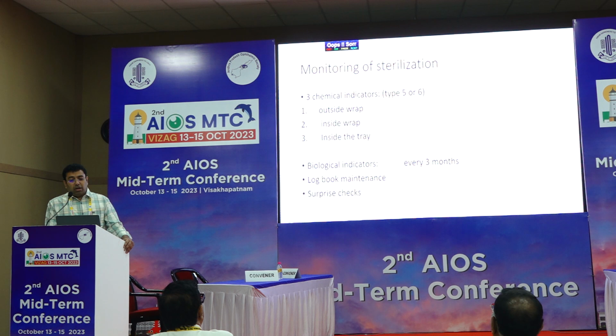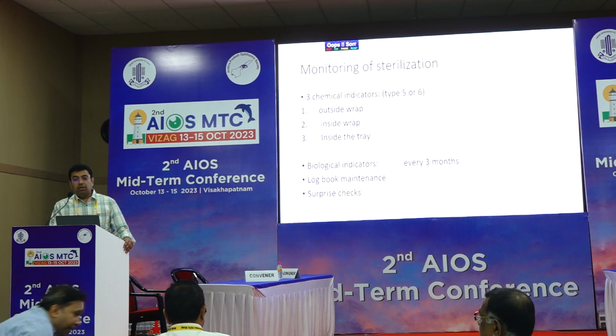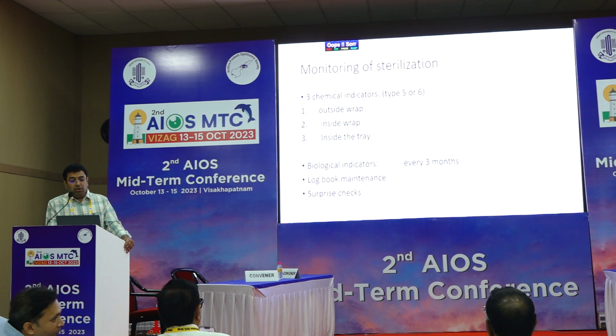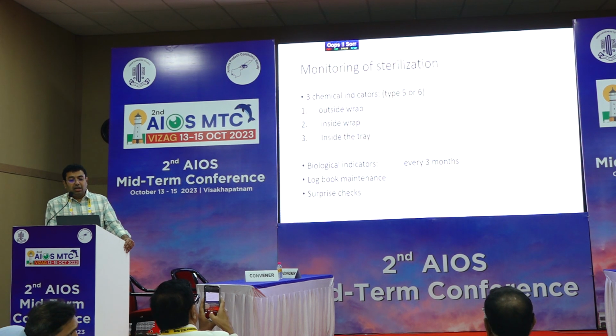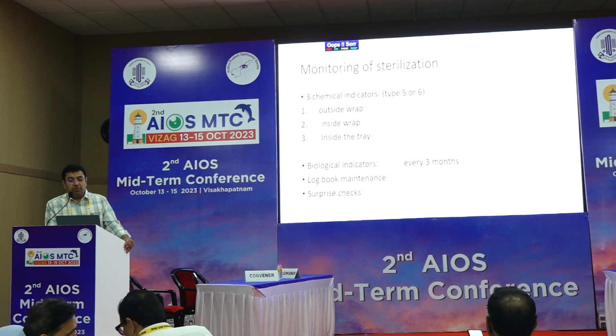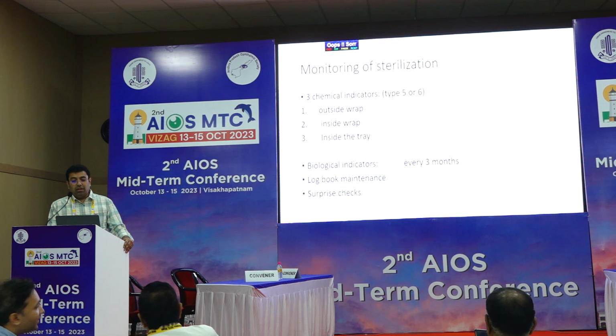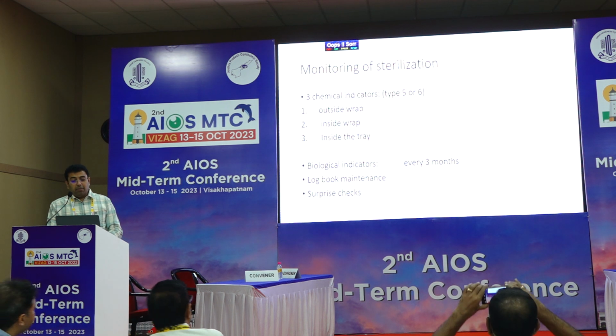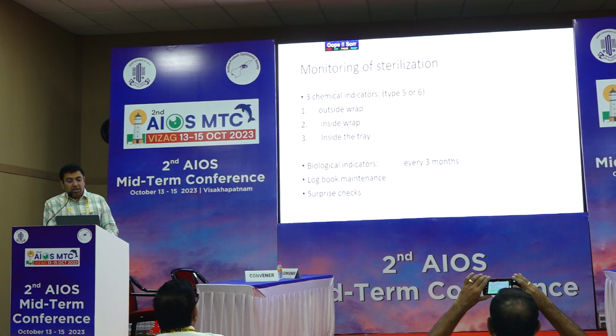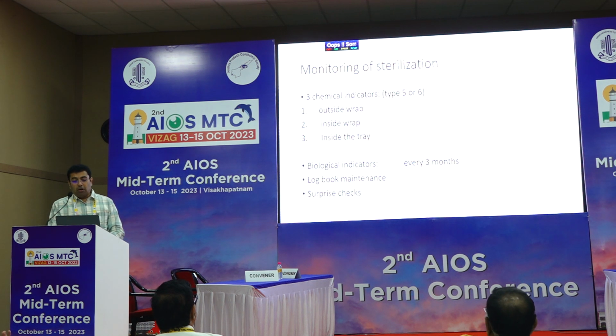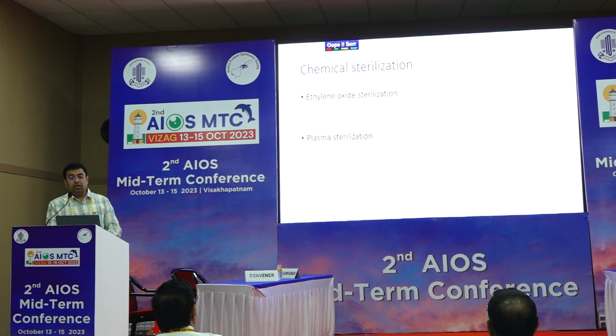So what are the AIOS guidelines for monitoring of sterilization? AIOS says that you should use at least 3 chemical indicators, type 5 or type 6. One you should use outside the wrap, one inside the wrap, one inside the tray. And if you are doing a large volume of surgery, biological indicators should be used every 3 months. And proper logbook maintenance and surprise checks of your sterilization process should be done.